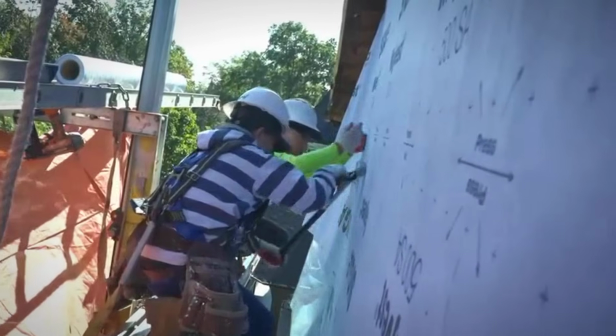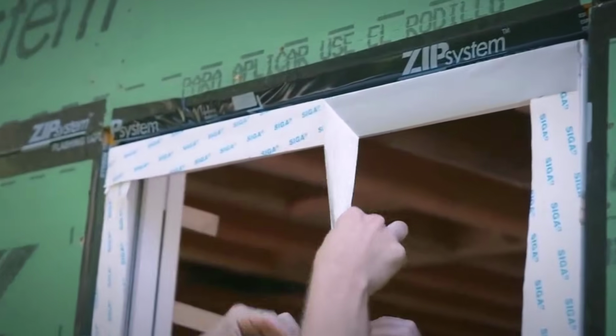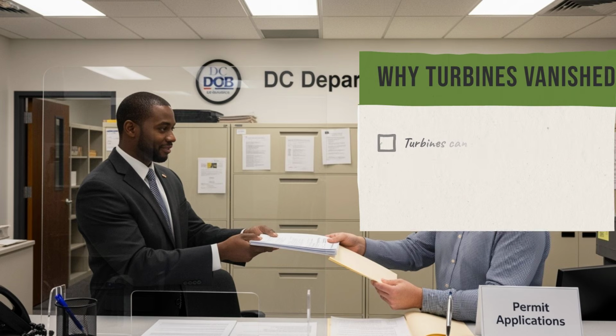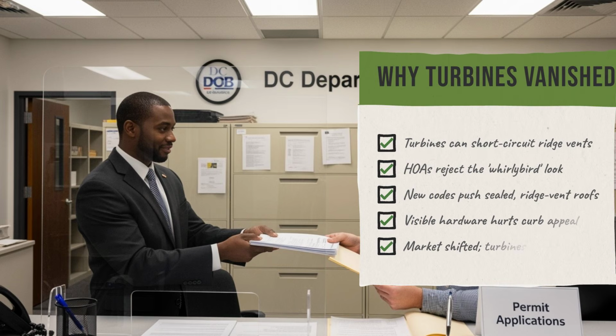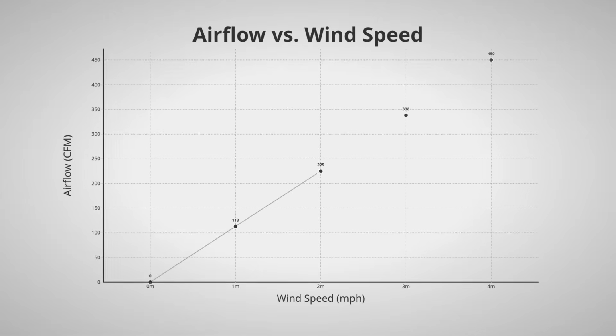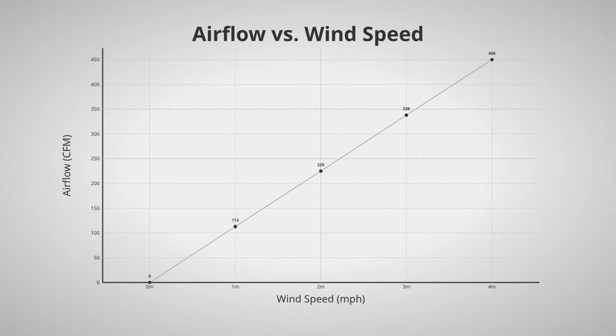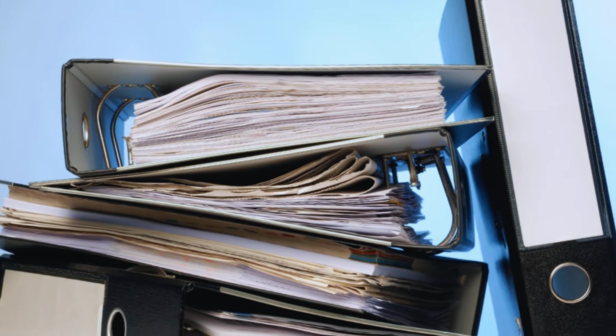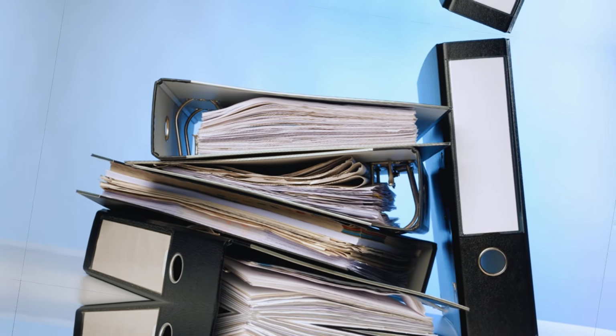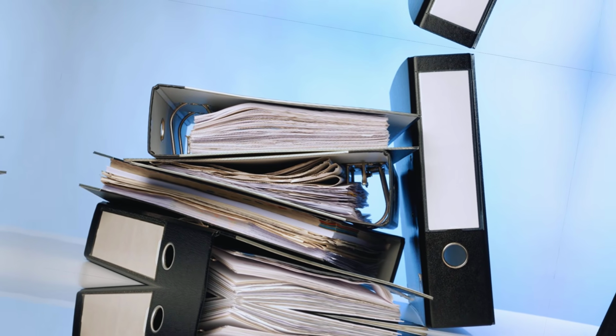Building codes have added another layer of difficulty. As American homes have grown tighter and more energy efficient, codes like the International Energy Conservation Code and California's Title 24 have begun requiring mechanical ventilation systems capable of guaranteeing precise air exchange rates. Because a passive turbine's performance depends on wind speed and ambient temperature, variables that cannot be controlled, it falls into a regulatory gray area that is increasingly difficult to navigate.